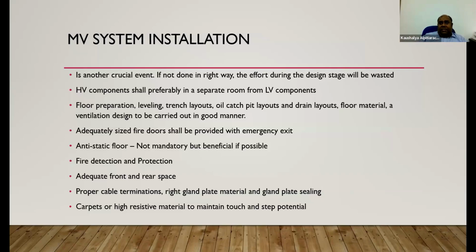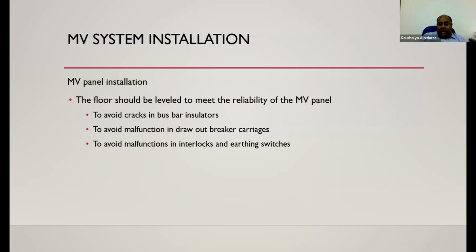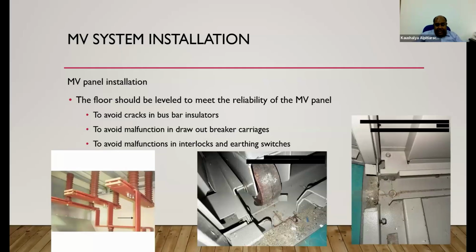I'll show you a few slides, few photos, of course. What happens is the floor level is not in order, and adequately sized fire doors at adequate locations. If possible, anti-static floor, fire detection and protection, adequate front and rear space for maintenance, testing, proper cable termination, right gland plate materials and gland plate sealing, carpets or high resistive material to maintain touch and step potential inside the indoor substation.